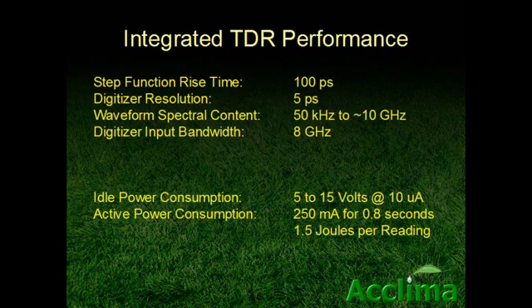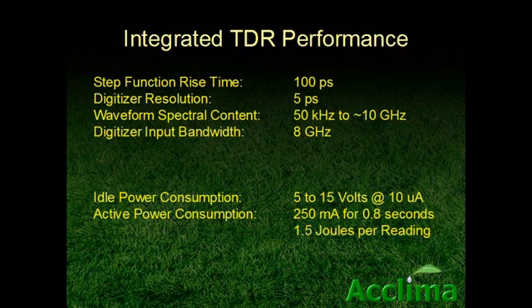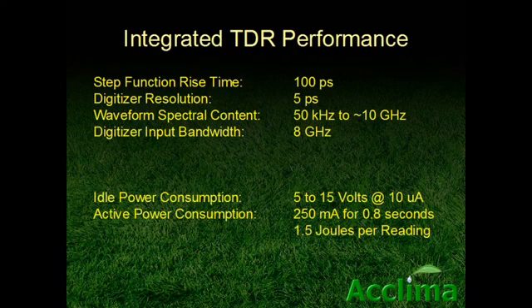Here's a summary of its performance. The step function applied to the soil has a rise time of 100 picoseconds, providing a very wide spectral content for the measurement of soil properties. There is no cable to disrupt wide bandwidth, and the receiver input has a bandwidth of 8 GHz. The digitizing resolution is 5 picoseconds, implying an effective digitizing rate of 200 billion samples per second. The reported permittivity and water content readings are immune to EC up to the point at which the signal is attenuated beyond reception. The device has an SDI-12 interface, runs on any voltage between 5 and 15 volts drawing 10 microamps in its idle state, and draws 250 milliamps for 800 milliseconds in its active state.